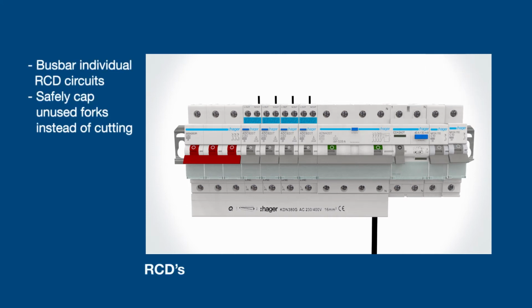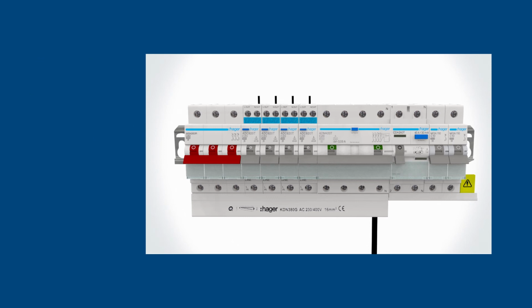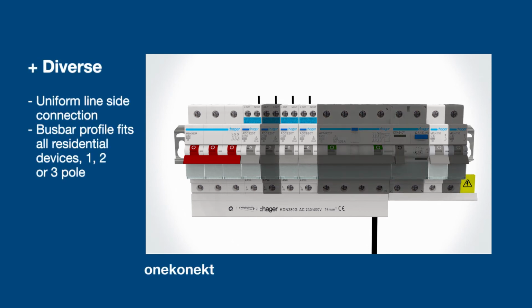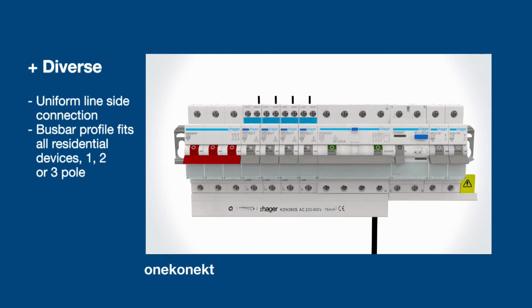When using separate RCDs with individual MCBs, smaller lengths of busbar can be used to keep the circuit separate. Unused forks can be safely capped to allow additional devices to be added in future if required. Our terminal profile is uniform on all our residential devices, MCBs, single or two-pole RCBO combos, or RCDs, whether they are single or multi-phase.